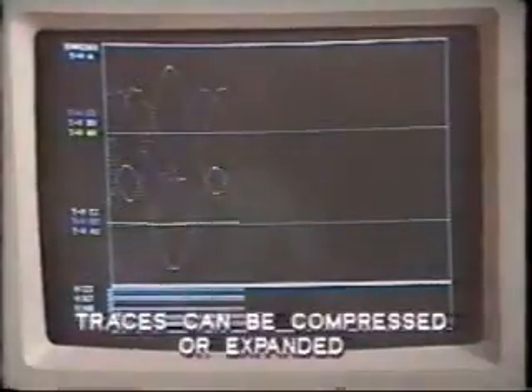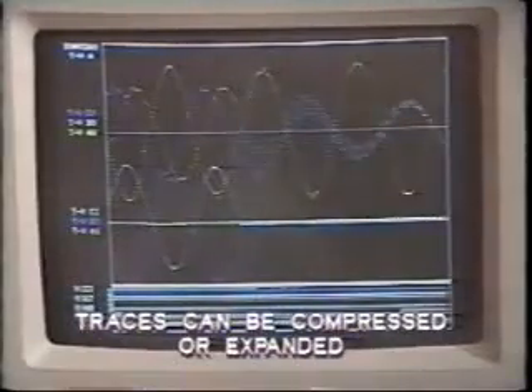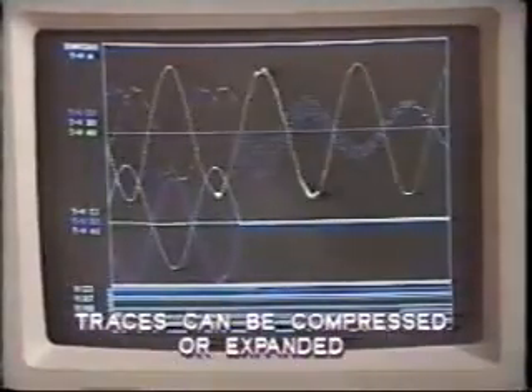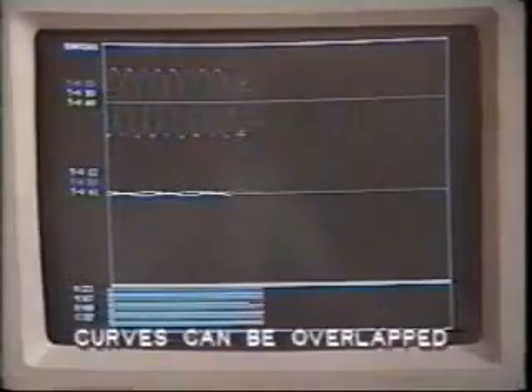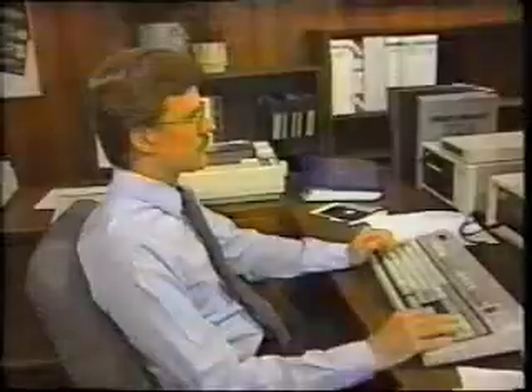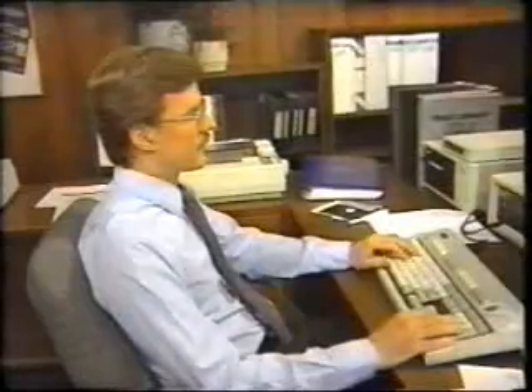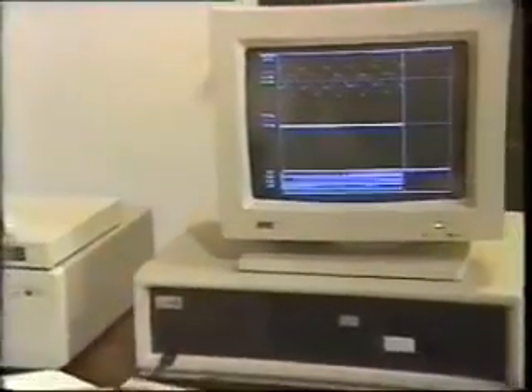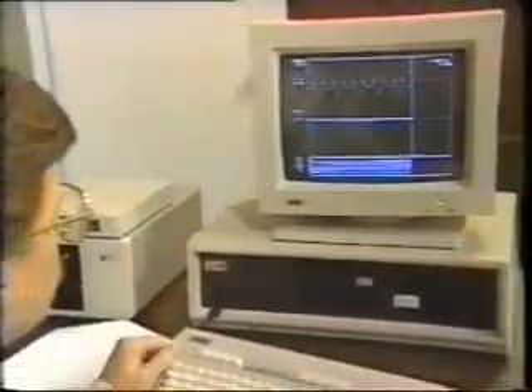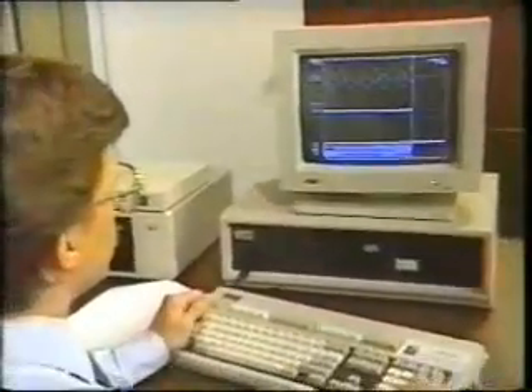Usually, the screen traces can be compressed or expanded in both time and amplitude so that a variety of signals can be compared. For precise examination, the curves can be overlapped. A distinctive advantage is the capability for immediate remote retrieval. Information from various locations can be brought into a master computer for analysis at a central location. In this context, another advantage is in the precise timekeeping of the digital system. Yet another advantage is the capability to adjust the individual trigger set points from remote central control.